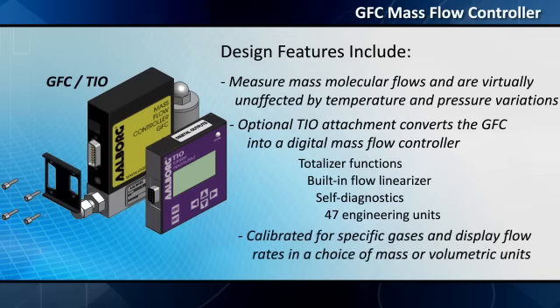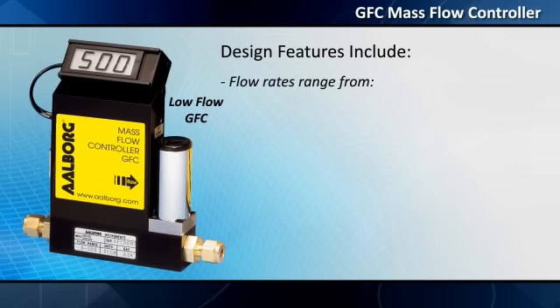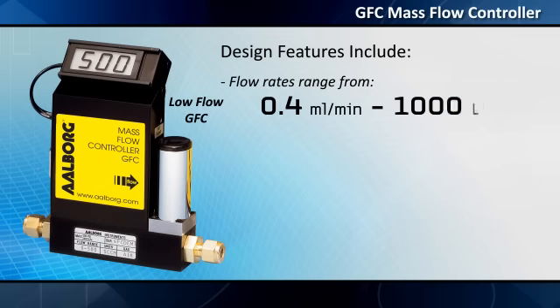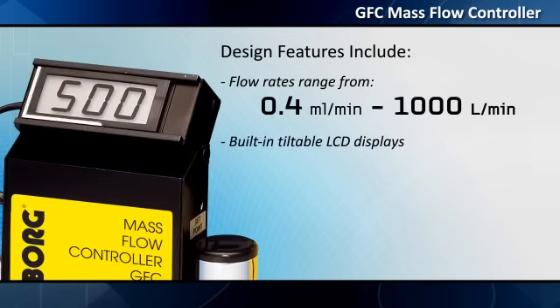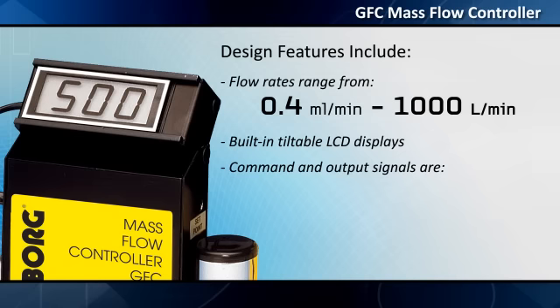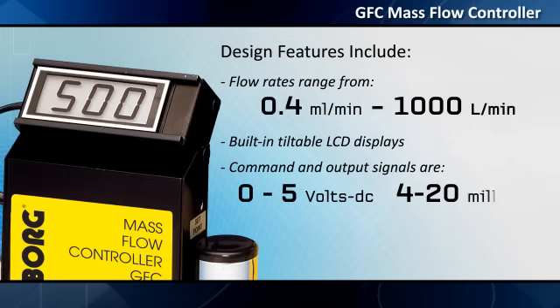Flow rates range from 0.4 milliliters per minute to 1,000 liters per minute. Built-in tiltable LCD displays are included. Command and output signals are 0 to 5 volts DC and 4–20 milliamps.